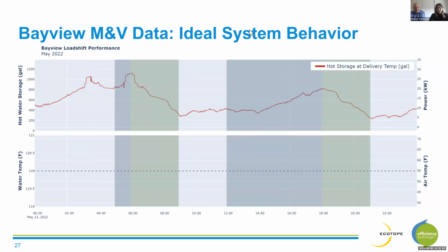And so the first data point we'll look at is available hot water storage in our primary storage tanks. The storage tanks at Bayview, there are 3 of them, and they each have 5 temperature sensors. So using this, we're able to get a snapshot of the tank's temperature profile at any point in time, which allows us to determine how much available hot water we have for the building.